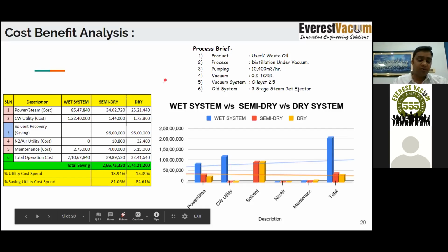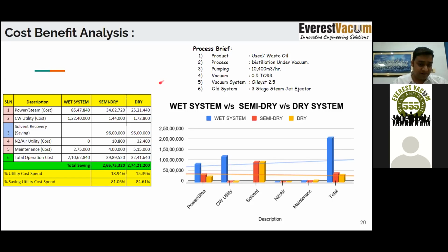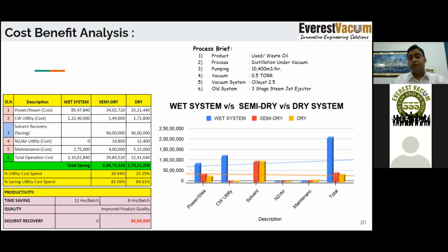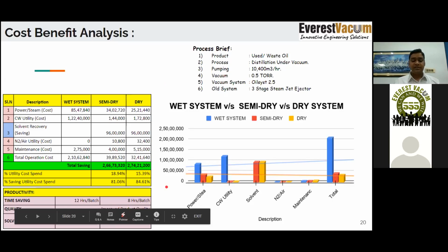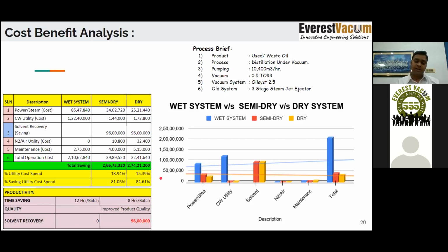The dry systems are quite efficient. They offer you 10 times more vacuum as compared to even semi-dry pumps. Yes, the maintenance cost is a little on the higher side, but the operational cost savings are very good. Coming to the productivity part, as you can see, the earlier batch time of 12 hours is now transformed into an 8 hour batch. So in a day you can now take out 3 batches instead of 2. You will save 1 batch entirely.